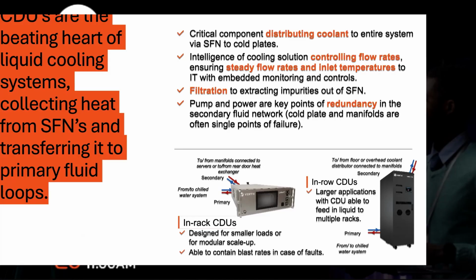Intelligence of cooling solutions means controlling flow rates, ensuring steady flow rates and inlet temperatures to IT with embedded monitoring and controls, and filtration to extract impurities out of the secondary fluid networks. Pump and power are key points of redundancy in the secondary fluid networks, while cold plates and manifolds are often single points of failure.